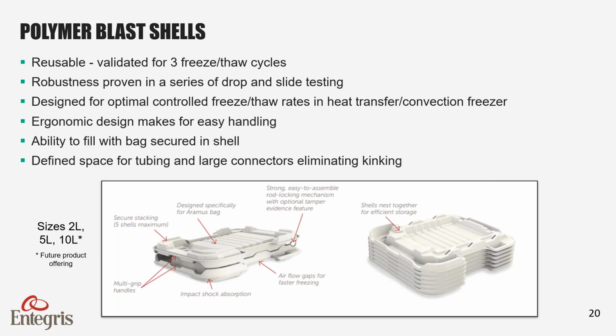Another key area was around ergonomics of using these types of pieces of equipment inside of the freeze-thaw workflows. Not only do you have employees in the facilities working with clean room gloves, you also have employees working with cryogenic gloves, because if these shells are transported at temperatures of -60 to -80 C, you need to have protective equipment in place to move those shells. So there's a number of different handholds designed to accommodate different sized hands to safely move those shells between places inside the facility.